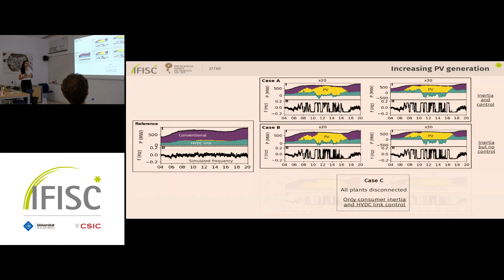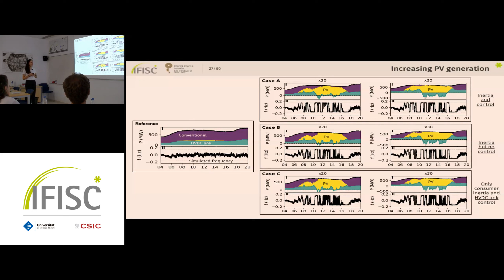So comparing those scenarios with increasing photovoltaic generation to the reference case, we can see that the fluctuations are much larger. However, the control provided by the high voltage DC link is enough to keep the fluctuations within the 0.15 Hz limit in all the cases. If we compare cases A, B, and C among them, we can see that the larger the inertia and control there is in the system, the less volatile the frequency fluctuations are. And we can actually see that better if we zoom in. You can see that here in this case, the frequency is varying very fast. And so although we are able to keep the frequency within the 0.15 Hz limit, it would be advisable to keep some inertia and control in the system just to avoid such high volatility.